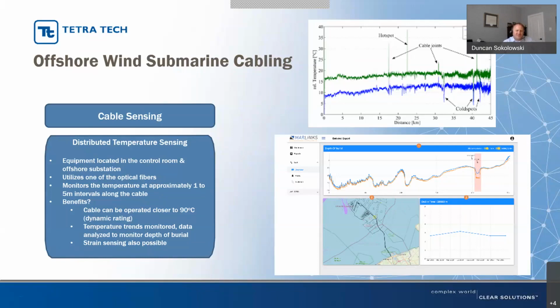It also gives you trends. So if the cable is running cooler than you'd expect for a given load, that could indicate the depth of burial is reducing, and that could give you clues about future remedial burial operations, so you can plan them in advance rather than having to do them in an emergency. Some countries, like Belgium, accept these systems in lieu of doing actual marine surveys, meaning less environmental impact and less cost. Hopefully some research will be done so that kind of philosophy could be applicable in other places.